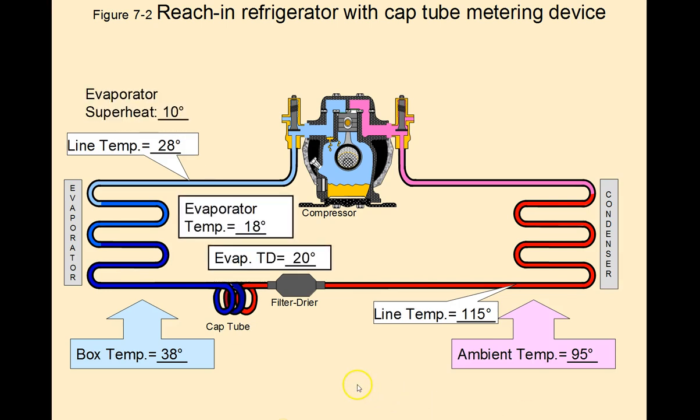So with a box temp of 38 degrees Fahrenheit, and you read on your gauges that you have an evaporator temp of 18 degrees, you're going to subtract that evaporator temp of 18 degrees from the 38 degree box temp for an evaporator TD of 20 degrees Fahrenheit, and your technician rule of thumb sheet will show you that that is a normal evaporator TD.